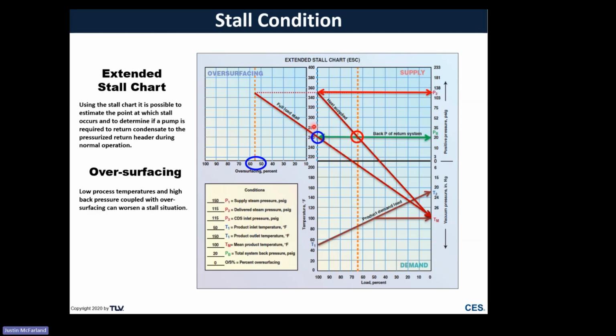So you can see in this scenario that 100% of the heat demands were already installed, meaning that no matter what this process heater is doing, from day one this customer is going to have problems operating this heater. They're going to have problems potentially with water hammer, with controlling temperature, with getting off-spec products, with gasket leaks, with all these issues that you guys are thinking of. And it has nothing to do with the heat exchanger. It has nothing to do with the trap itself. It's just a mismatch on the drainage solution with that process and what that process heater is doing.